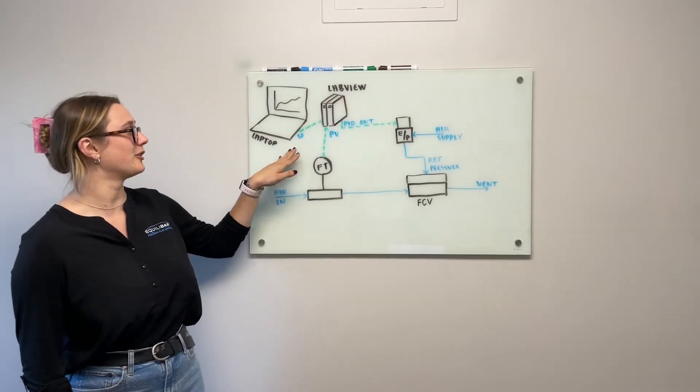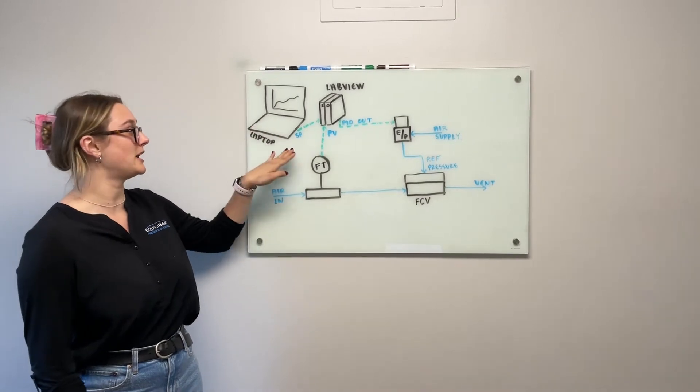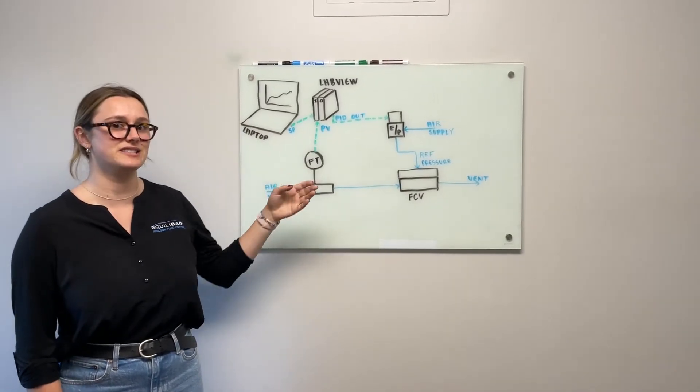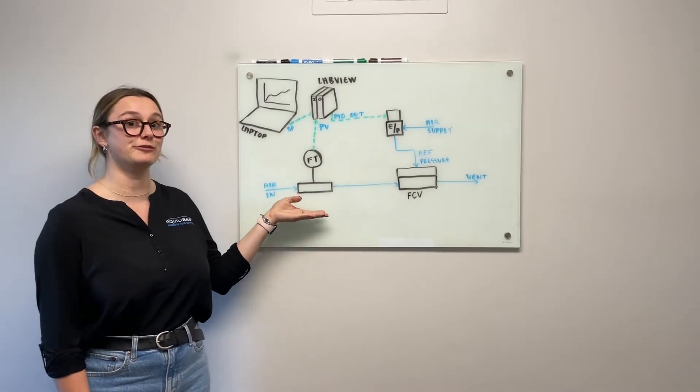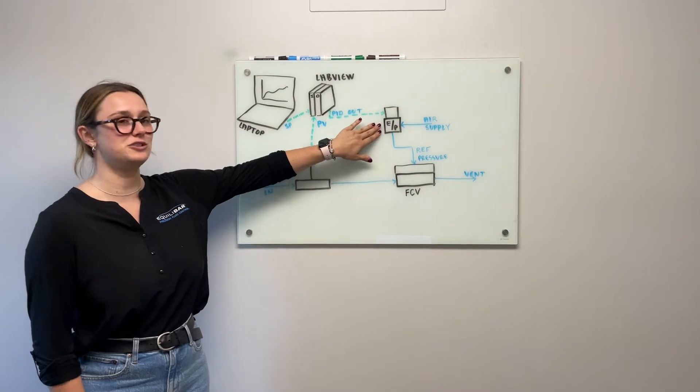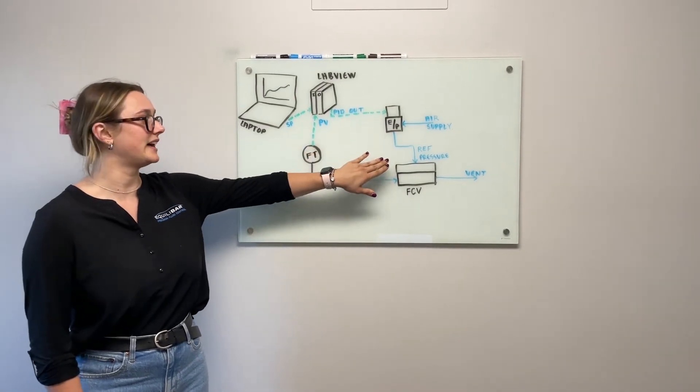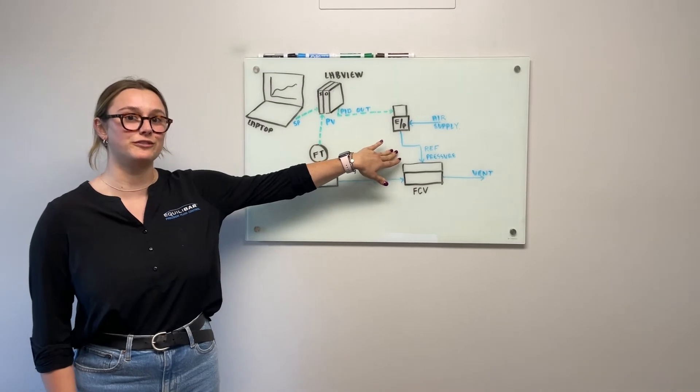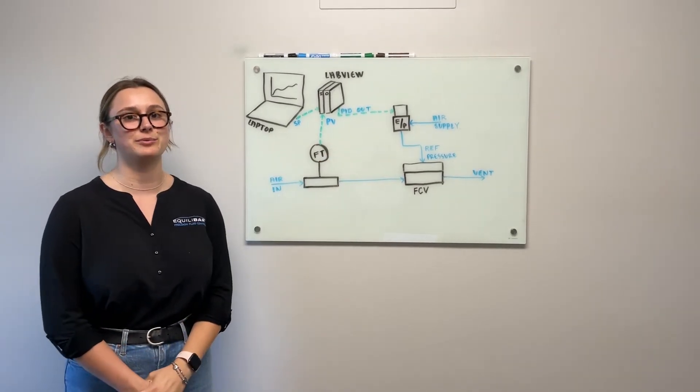We're giving the program a set point from this laptop. It is being compared to the process value, which is in this case the flow rate as measured from our thermal flow meter, and then the program is giving a PID output value to our QPV. That is ultimately changing the reference pressure on our Equilibar flow control valve to help reach the flow set point in the system.